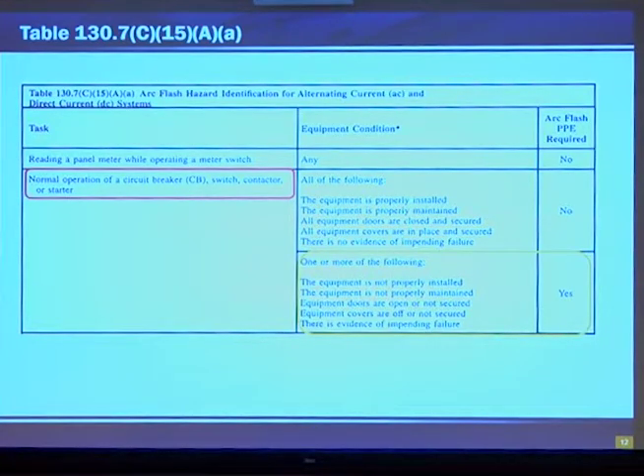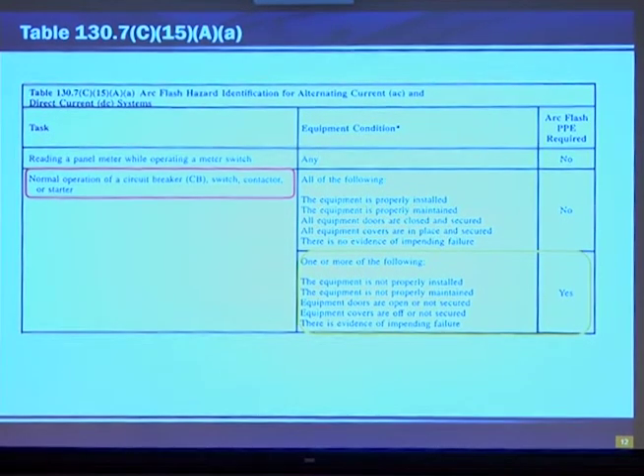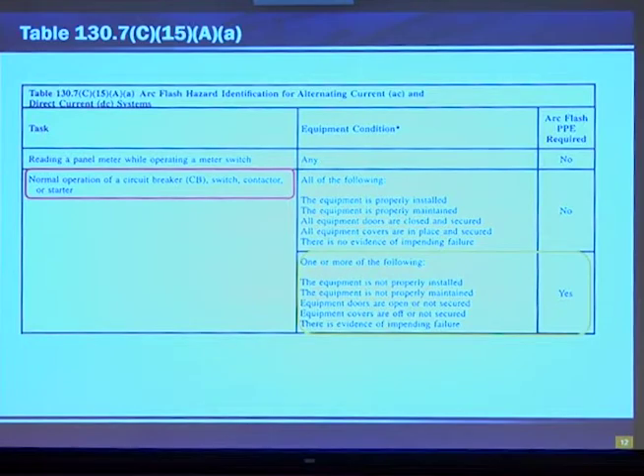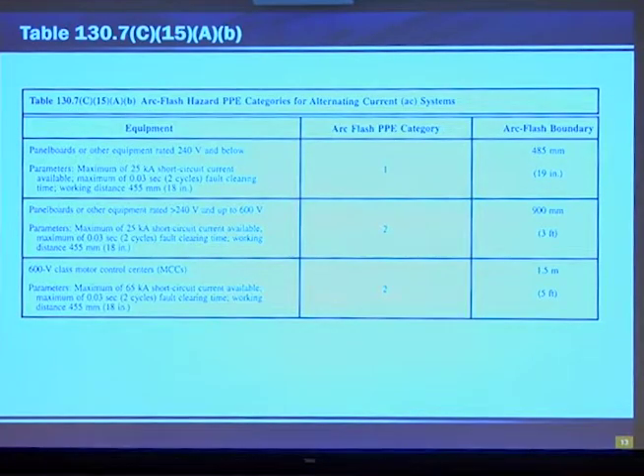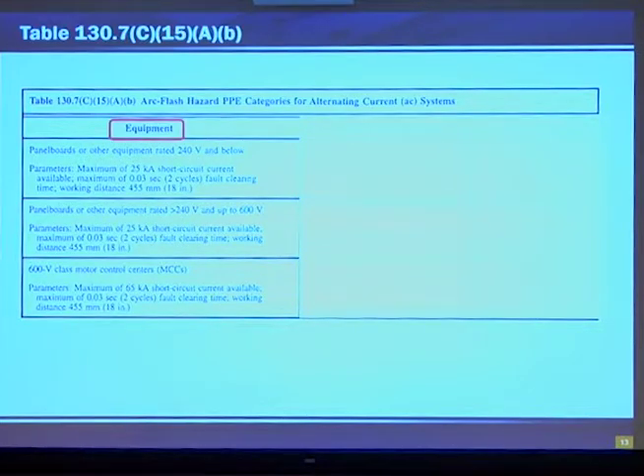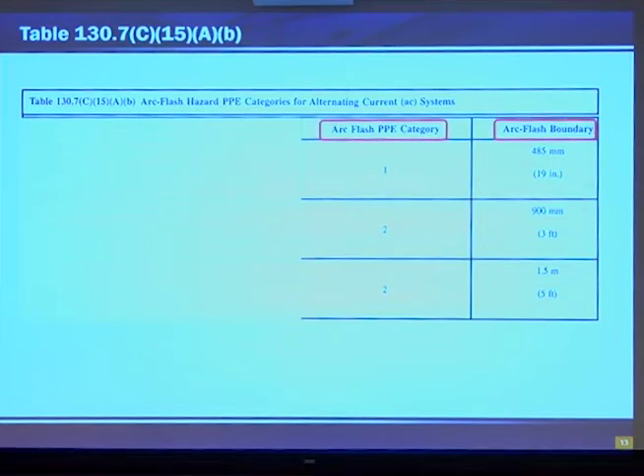So once you know that the PPE is required, what now? Well, now we got to go to table B to figure out what PPE is needed. Table B, I'm going to say this long one just so y'all can hear it one more time. 130.7C15AB. That's a mouthful, I'm telling you. On the left-hand side is the equipment. Tell you the equipment and the condition. On the right-hand side will be the ArcFlash PPE category and the ArcFlash boundary.